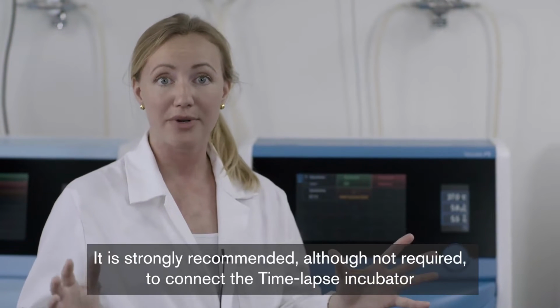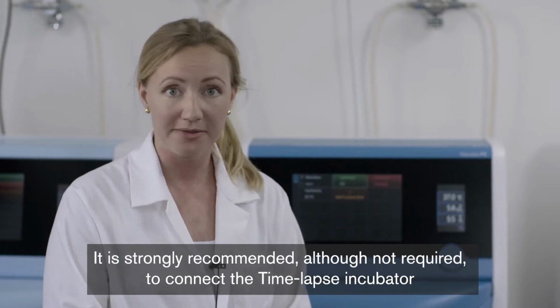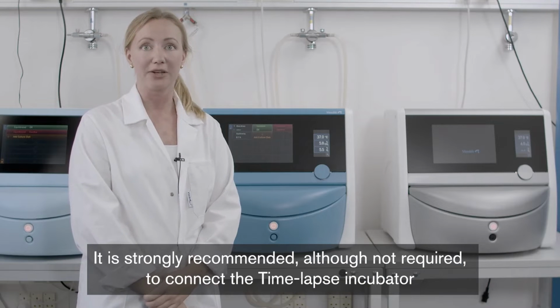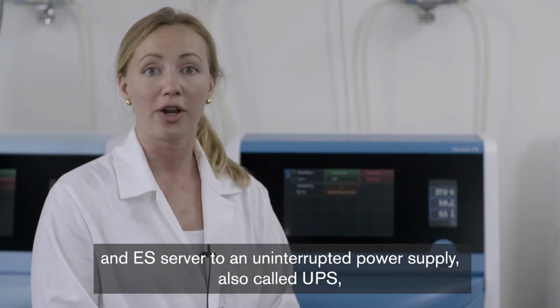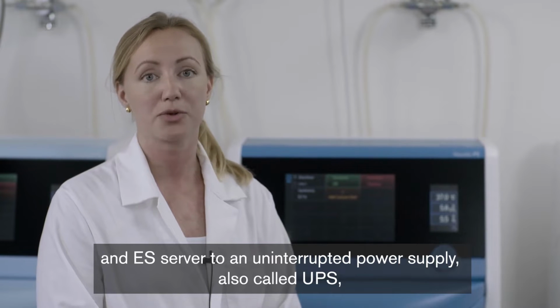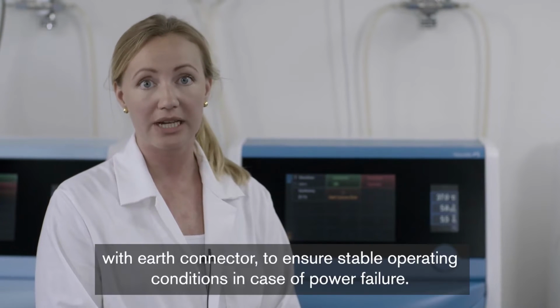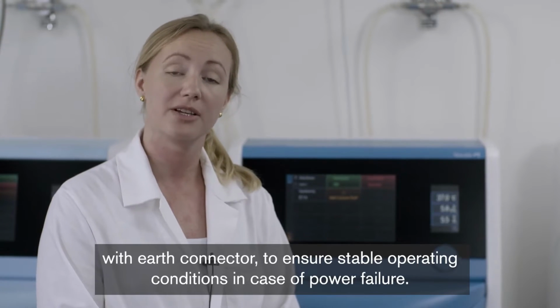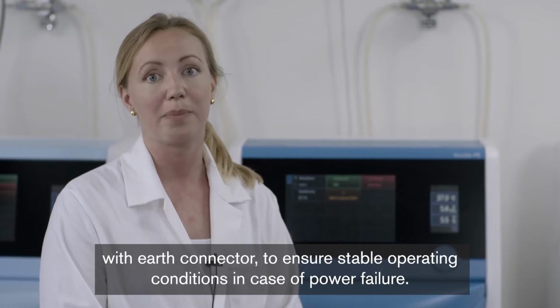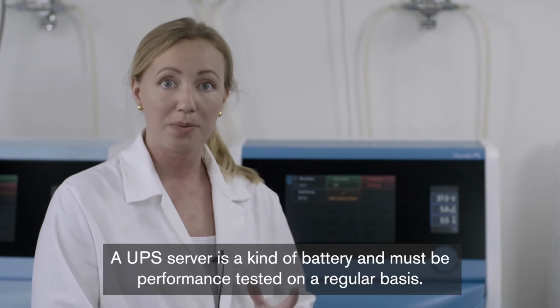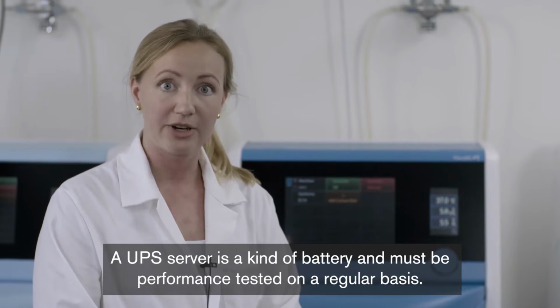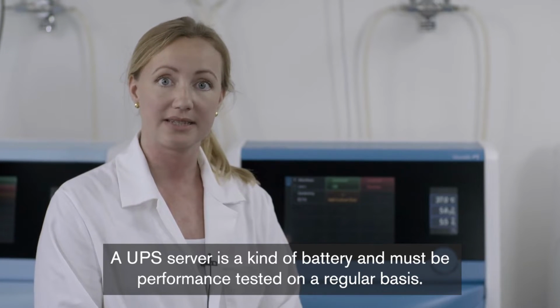It is strongly recommended, although not required, to connect the time-lapse incubator and ES server to an uninterruptible power supply, also called UPS, with earth connector to ensure stable operating conditions in case of a power failure. A UPS is a kind of battery and must be performance tested on a regular basis.